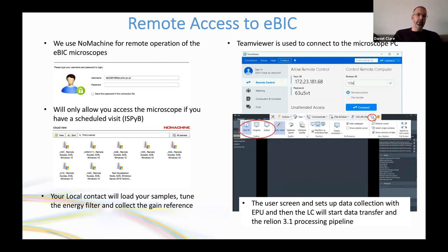For each remote microscope session, users access the microscope via NoMachine using Diamond credentials during a window roughly one to two hours either side of the scheduled time. The local contact loads the samples, tunes the energy filter, and takes the gain reference before handing control to the user. Users then connect via TeamViewer to the microscope PC for screening and EPU session setup.